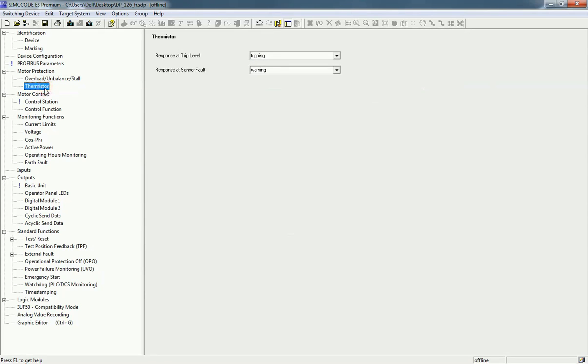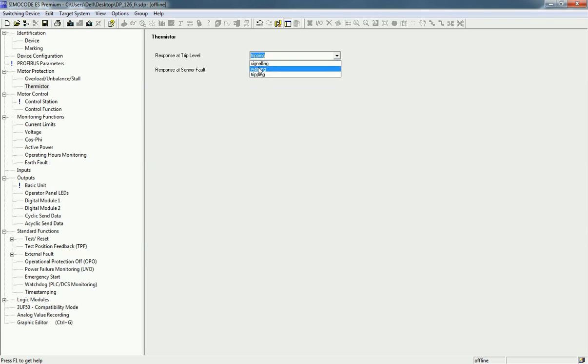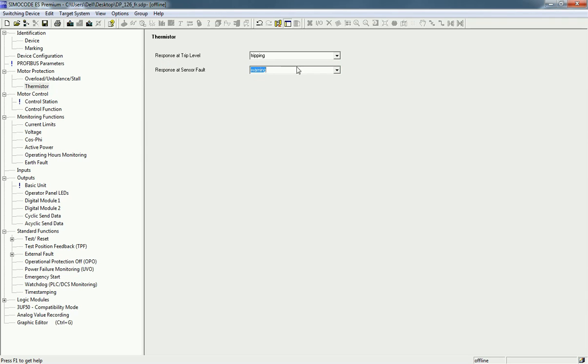Next we go to Thermistor. If you are using a thermistor for temperature measurement, you have two options. For response at trip level — when the thermistor reaches a critical level — you can select signaling, warning, or tripping. For response at sensor fault, we will select warning because a sensor fault can be due to physical damage or a communication error. For the response at trip level we will go for tripping, because the thermistor reaches a critical level only when the motor heats up.